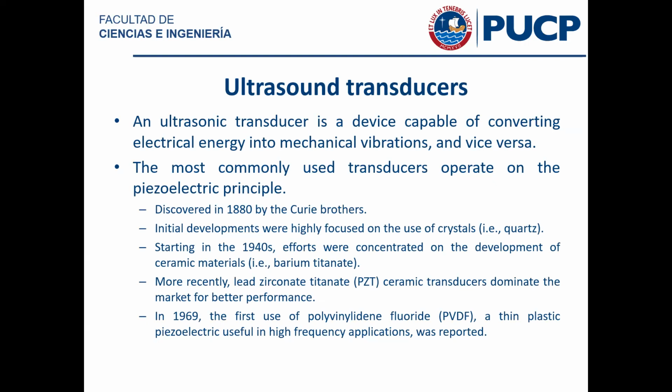So we should start with ultrasound transducers. First, a transducer is a device that can convert electrical energy into mechanical vibrations and vice versa. It's like a microphone for recording and a speaker for sound generation, both at the same time. Technically speaking, transducer just means that you can convert one type of energy into another. Ultrasound transducers allow you to do this both ways, and of course there are other devices for other types of energy that allow you to do it both ways too.